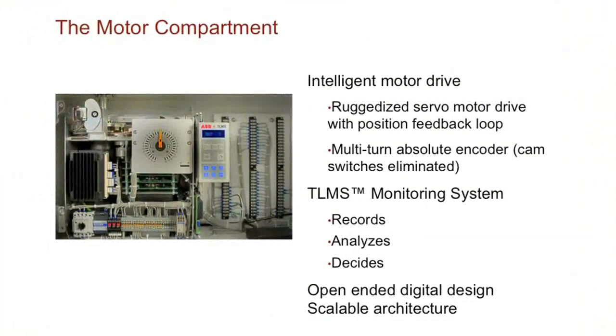In the industrials, you'd go through this pretty quick. On the utilities, you'd probably get up into the 15, 20-year range sometimes. Like I say, it strictly depends on where the unit's operating. The intelligent motor drive, basically it's a servo motor with a position feedback. Then we have a multi-turn absolute encoder, basically eliminating all the cam switches as well. The TLMS monitoring system records, analyzes, and decides, it makes all the decisions for this LTC when it's in operation. It gives you the phase angle when it's changing positions, so you can do maintenance checks with it in service, which allows you to check your timing and things of that nature.